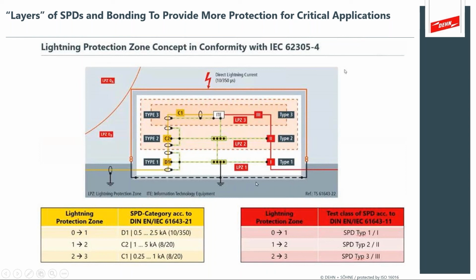So here you might have your main electrical service entrance, and that might feed a branch circuit on the floor of a hospital, which ultimately goes into a very delicate operating room. So this is a great example of the more protected zone having more control of risk. And IEC does a great job of providing guidance into how to select the devices, where to place them, and then how to bond them in with your electrical service.